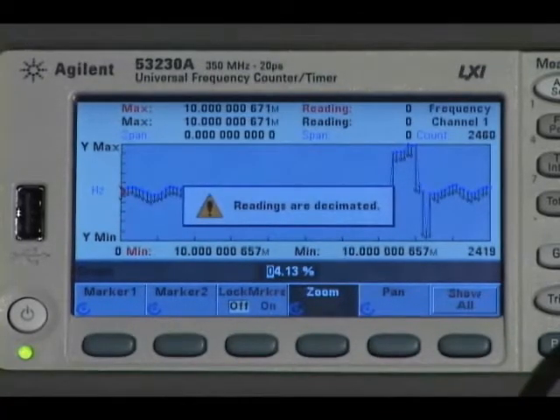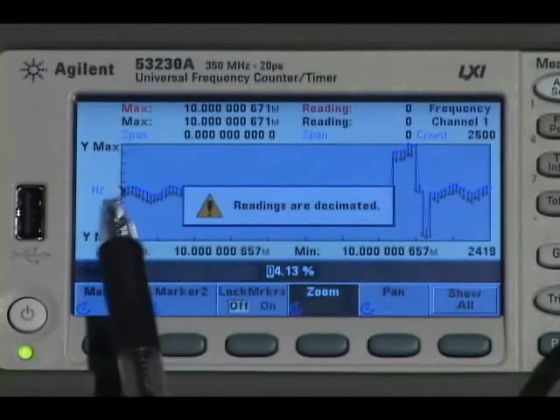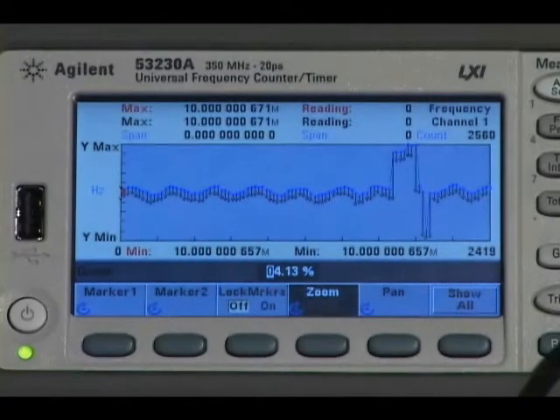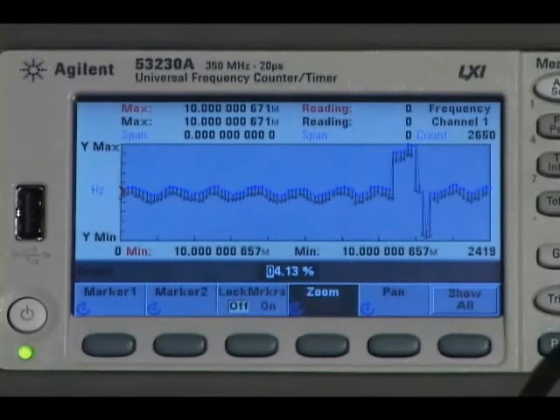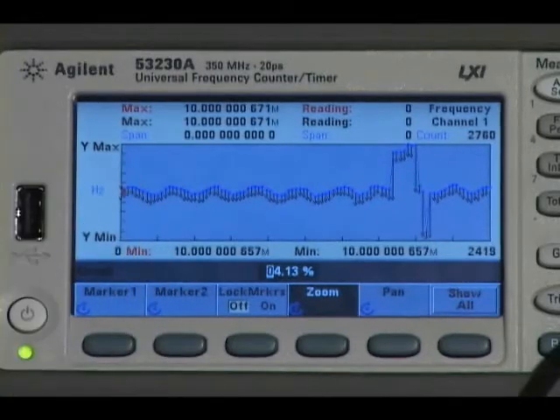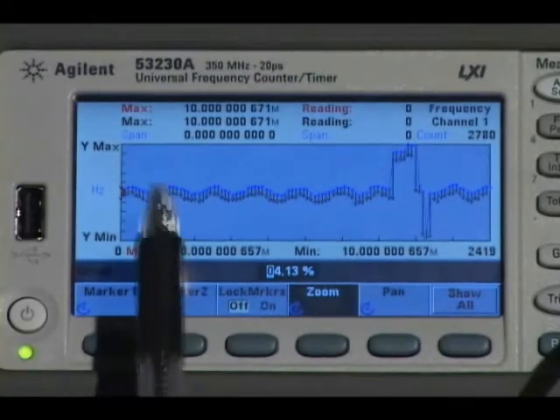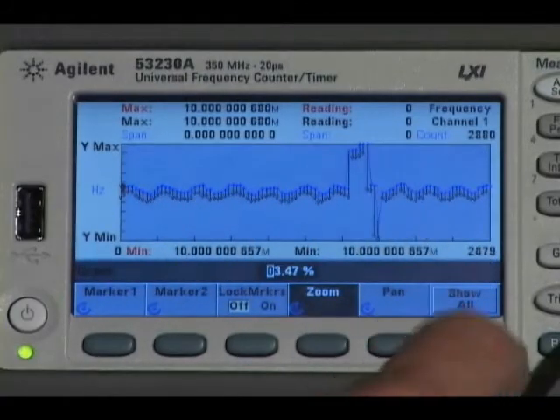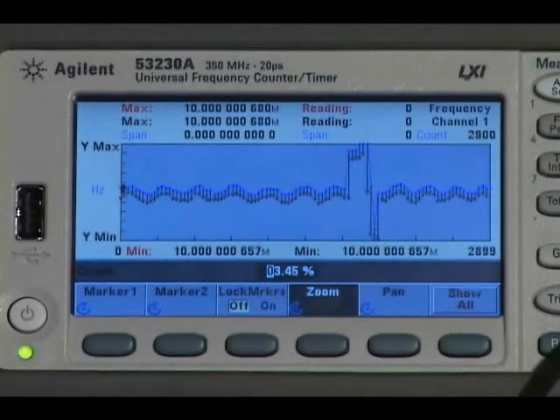What's introduced here is a representation of all readings. 2300 readings were decimated into 100 readings, so 2300 divided by 100 would be 23 readings per group. Each group shows a max and a min, so you can actually show the entire range of readings thus far, and you can continue to push 'show all' to see what's happening.